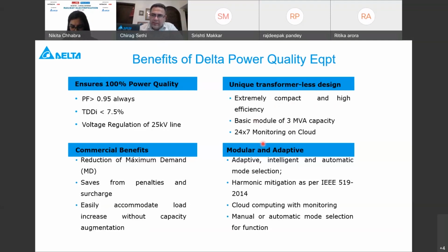It is modular in nature. It has 24/7 monitoring. It complies with the latest IEEE 519 standard. One more thing I would like to mention here: manual or automatic mode. As a user, the user can set his priority, whether he wants to address the requirement of power factor first or harmonics, and accordingly set it as a parameter on the HMI. In case of Southern Railway, let's say the penalty was coming due to harmonics, so the capacity of our equipment was first used to bring the harmonics within the requirement, and the balance amount of rating to the compensating current to cater to the power factor improvement.